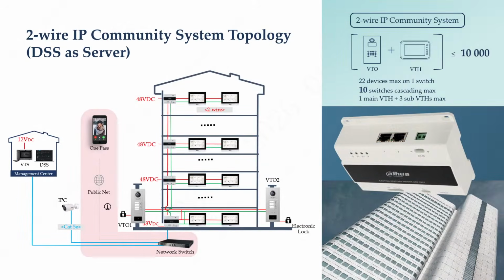Yeah, that module called VTNS 2003B-2. This module is, let's say, the level module. It needs to be supplied with 48 volt DC. And one thing is really important about this module. It has an up and down port, so you can cascade 10 VTNS into one line.